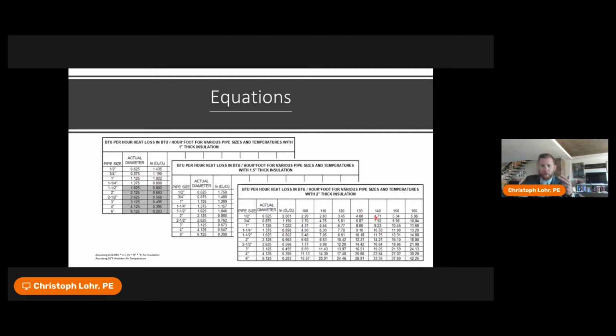Most of this piping in a hot water system tends to be 2 inches or smaller in most cases, especially if you're utilizing the water demand calculator. You can get the smaller pipe sizing. So in essence, what has happened, especially in some facilities where this 30 BTU per hour per lineal foot has been used, is the hot water return system dictates the supply sizing.